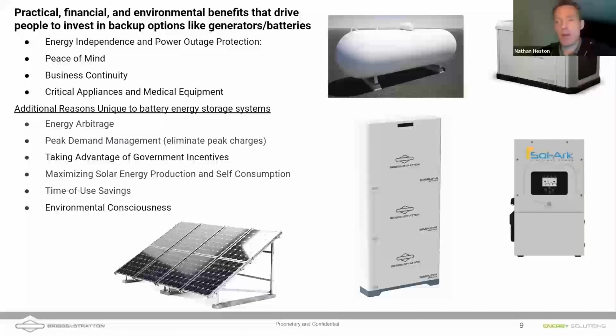You can limit the amount of power that you're pulling from the grid. You can use some CTs, monitor what you're pulling from the grid, and be exporting that back to your panel so that essentially it zeroes out your meter. You're not pulling anything from the meter. You can also take advantage. There are a lot of government incentives out there for having backup power in homes and having solar, right? Having green and renewable sources. And these are there because the grid needs that help, right? The grid is in many cases struggling with this increased demand, and utilities want us to have backup power.